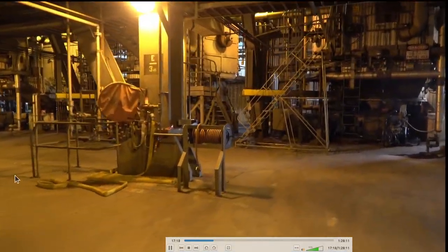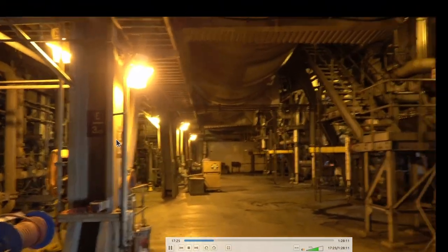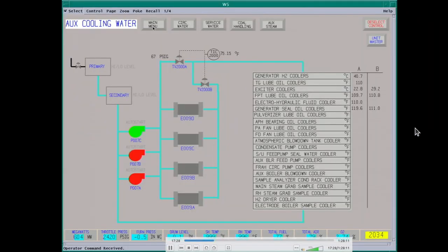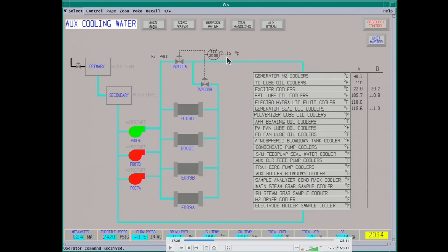Another pulverizer is on the south side. This is the aux cooling water system — a simple system but very important. It has really clean water, so they use dirty service water through the heat exchangers to cool your aux cooling water. All your aux cooling water goes through the plant fairly clean — you don't plug up heat exchangers and you don't corrode them. It's temperature controlled, simple, but really critical.